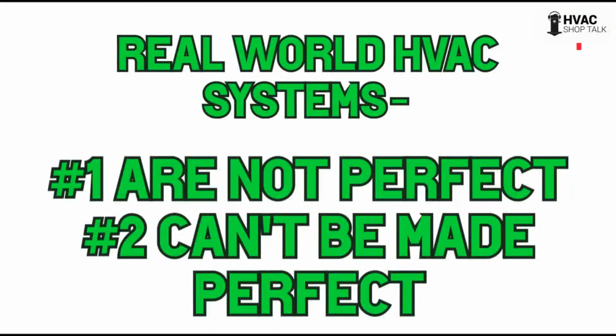All right, so real world HVAC systems. I want to tell you, a lot of you know this already, they're not perfect. They're not installed correctly, not ducted correctly, not charged correctly. They don't get enough air, or they get too much air. The duct's too small or too large, it's not made correctly, it leaks. They left the door off of it. Gas pressure is not right, too high or too low, or they use the wrong piping. There's all sorts of things that lead to a job not being done correctly.